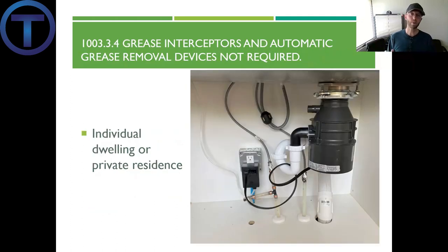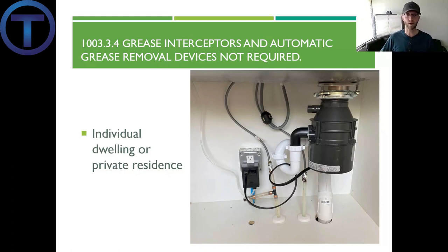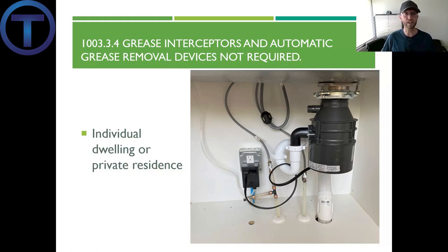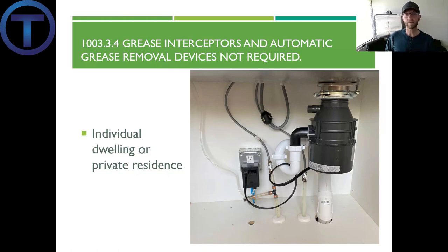Section 1003.3.4 states that grease interceptors and automatic grease removal devices are not required in individual dwellings or private residences — this is why you don't have a grease interceptor in your own house. That doesn't mean grease waste isn't going down the drain; in fact it does, and the less grease you put down the better. But on an individual dwelling, there's not as much grease as you'd find coming from a commercial kitchen, so they don't require the same separation.